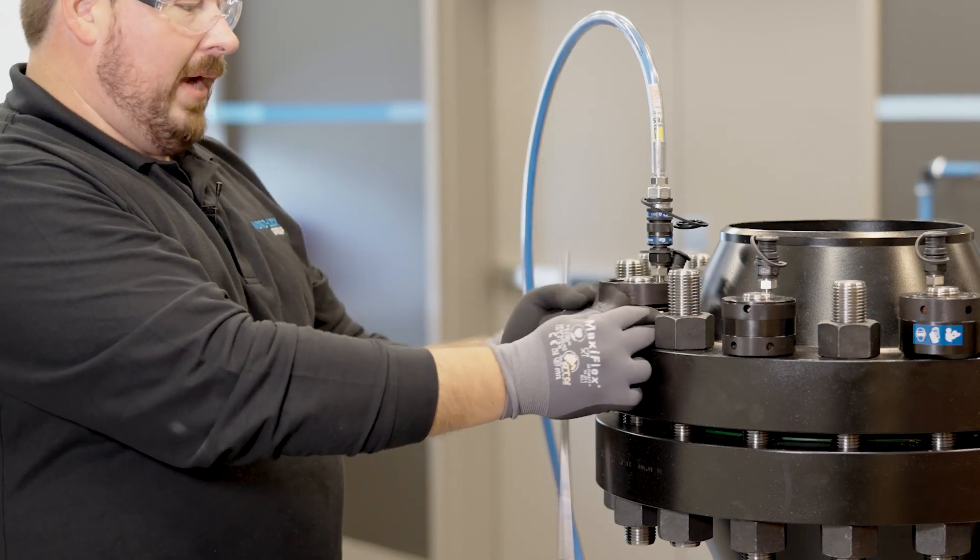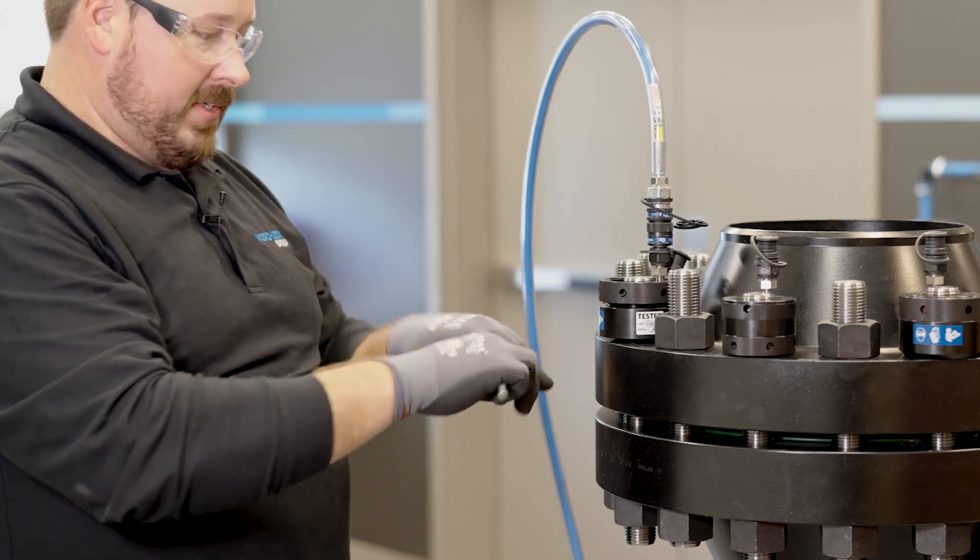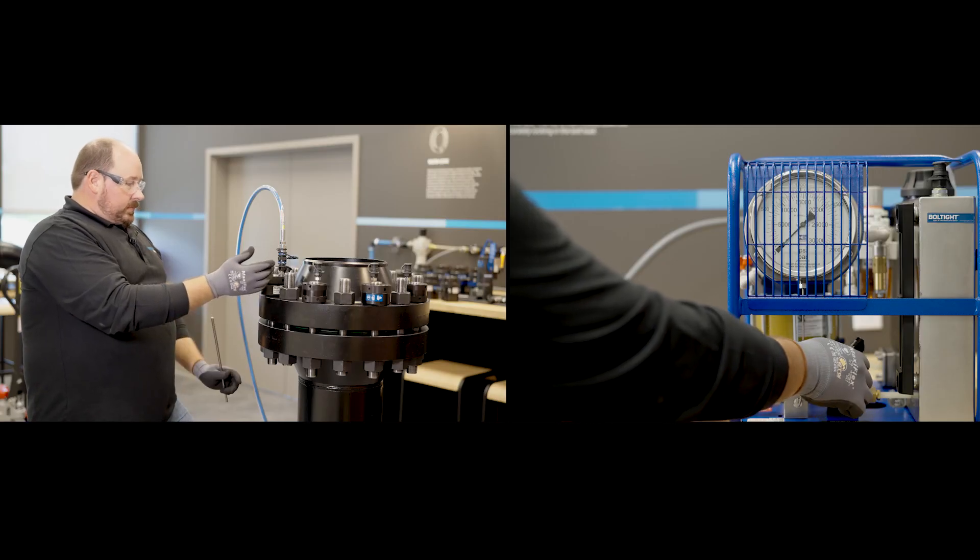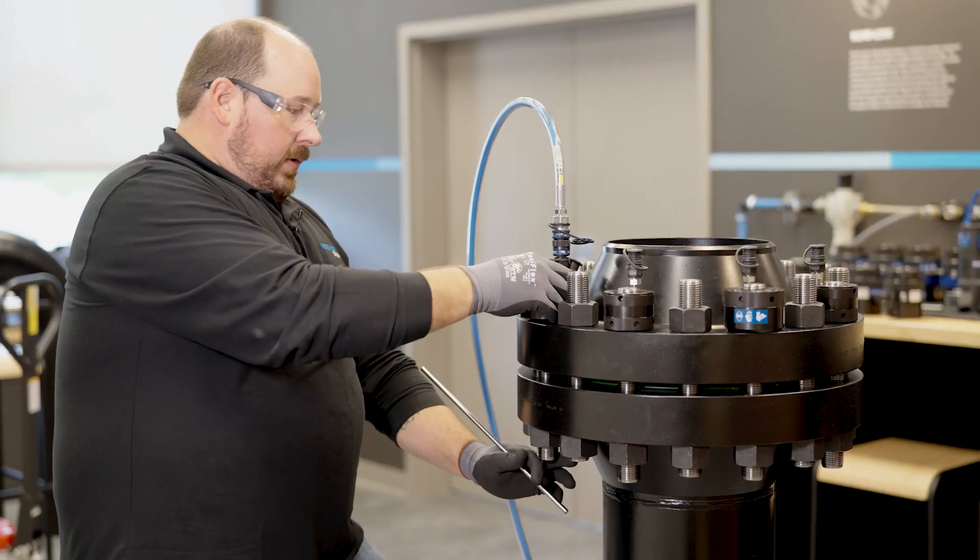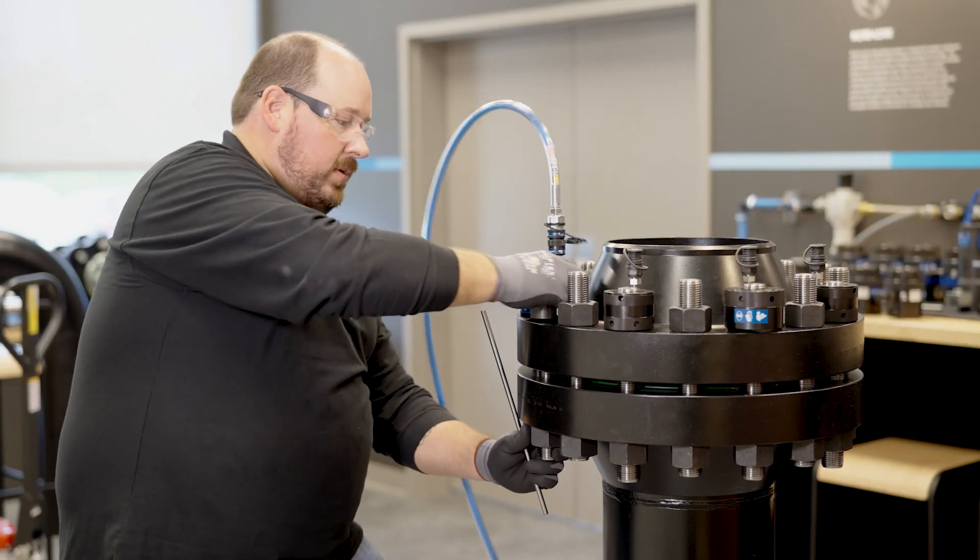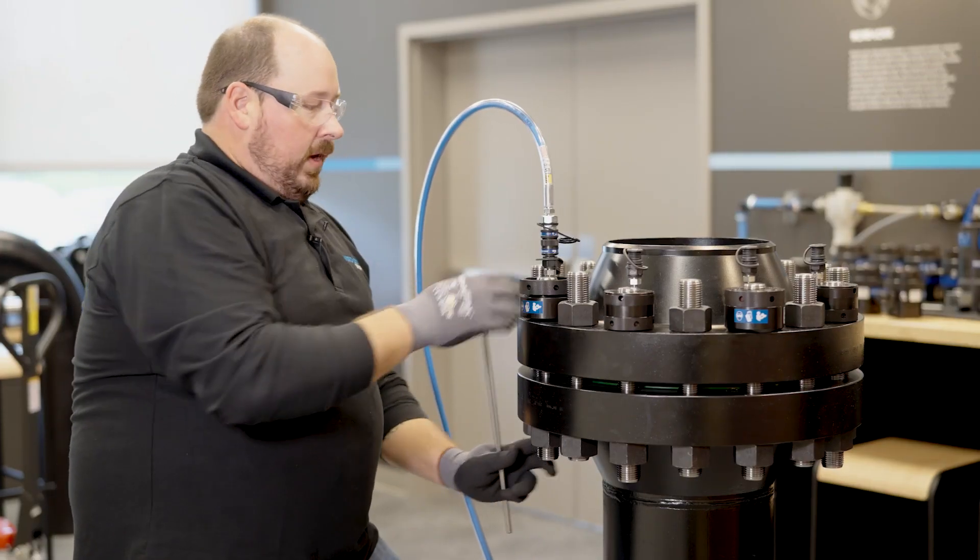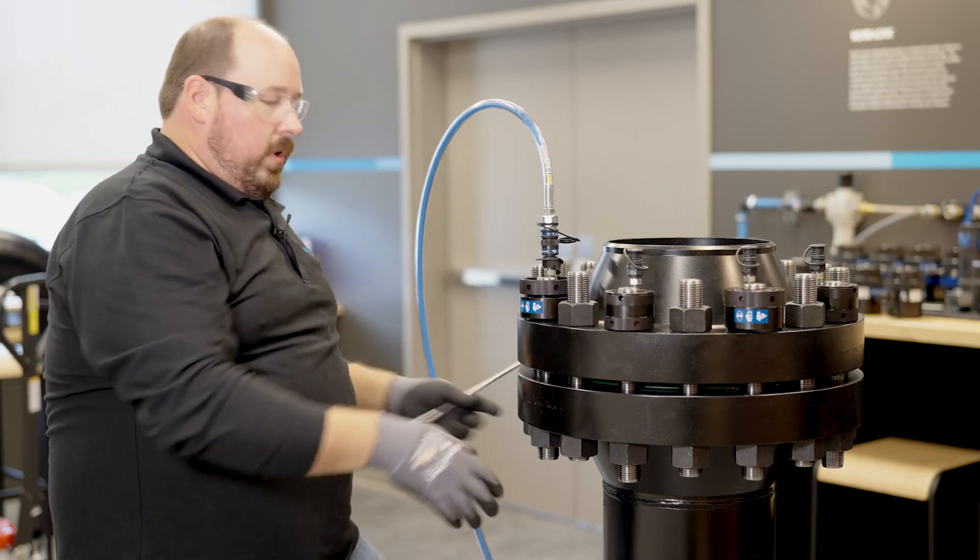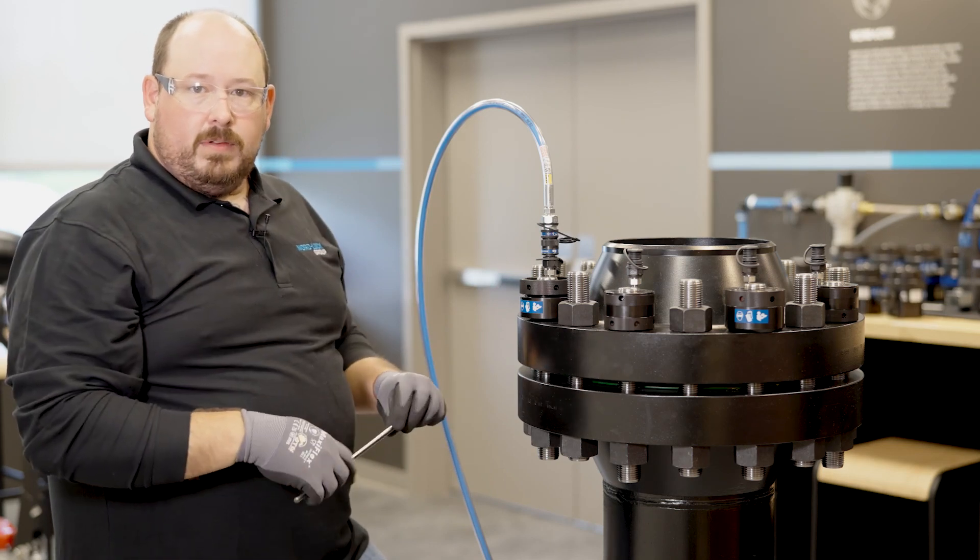Now once you get it broken loose, you just want to back the collar off so that when it relaxes, it doesn't lock down again. So go ahead and release. All right, there we go. Now the nut's loose and I can turn it with my hand, and then we'd simply do that all the way around the flange. We come off the nuts and pull all the bolts out and do whatever work you need to do after that.